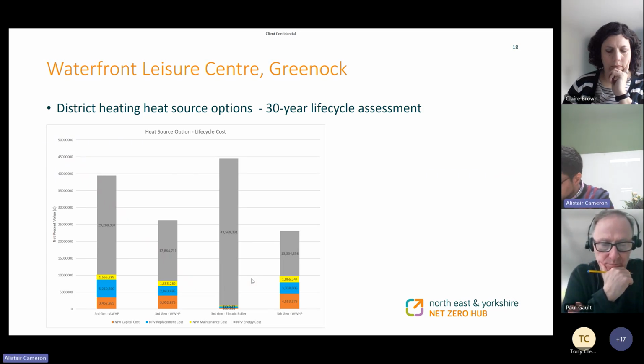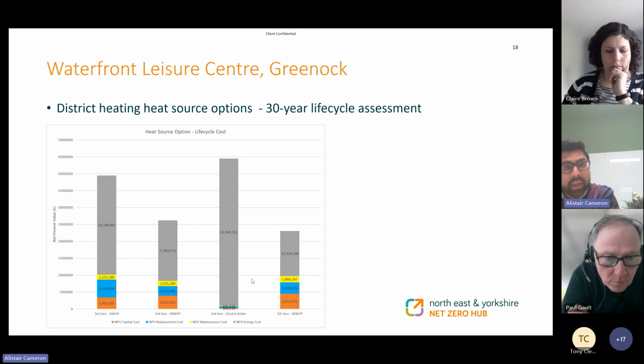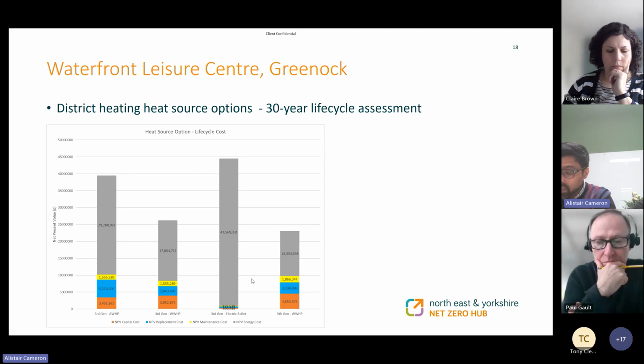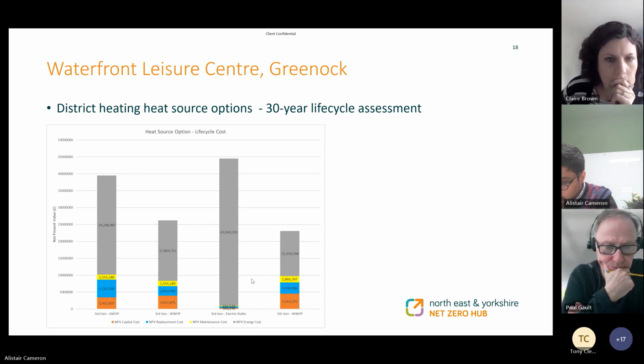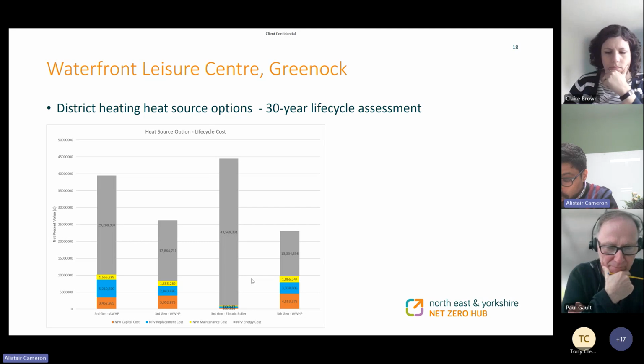Now, looking at the 4 options that we presented to the client, we did an analysis based on life cycle. So we looked at over a 30-year period how much each option would cost to operate. So you've got your bar graph. The grey bar indicates the energy cost, so that's your operational cost over that 30-year period. The yellow section is your maintenance costs over that 30-year period, and blue is the replacement cost of plant, and the orange is the initial capital cost.